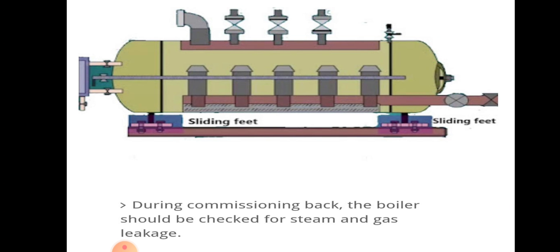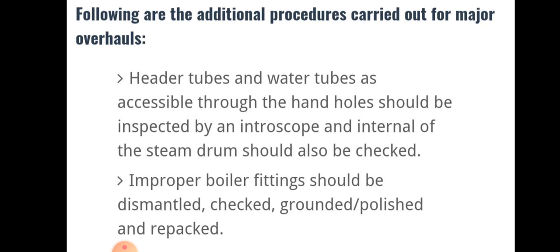During recommissioning, the boiler should be checked for steam and gas leakage. Then the additional procedures after major overhauls: header tubes and water tubes accessible through hand holes should be inspected through an endoscope. The internals of the steam drum should also be checked.